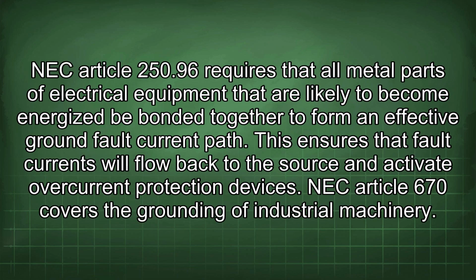NEC Article 250.96 requires that all metal parts of electrical equipment that are likely to become energized be bonded together to form an effective ground fault current path. This ensures that fault currents will flow back to the source and activate overcurrent protection devices.